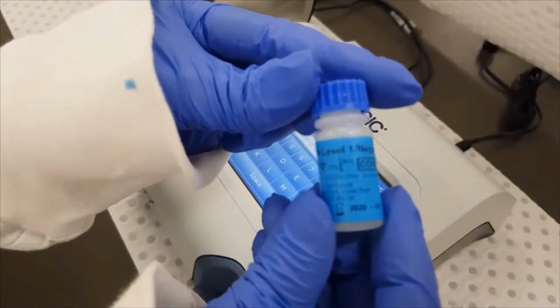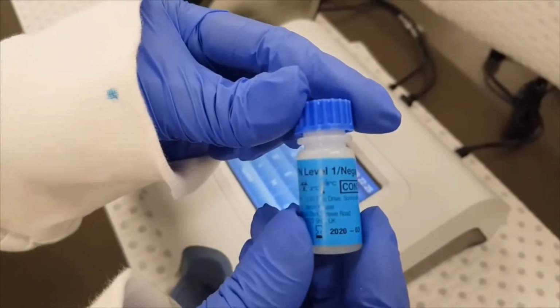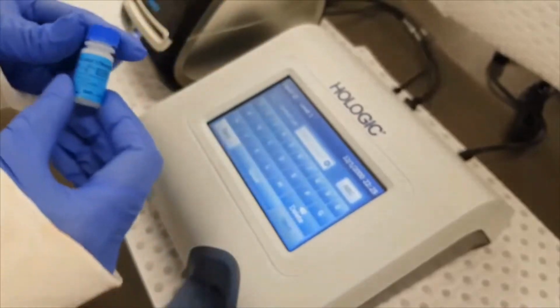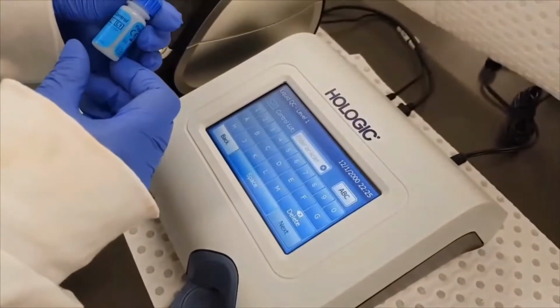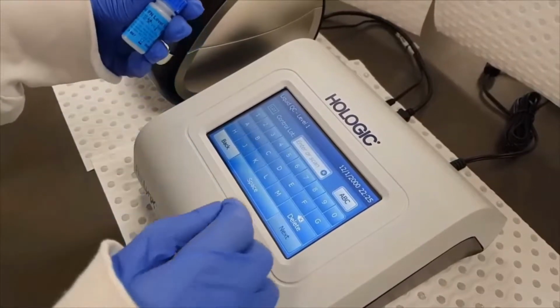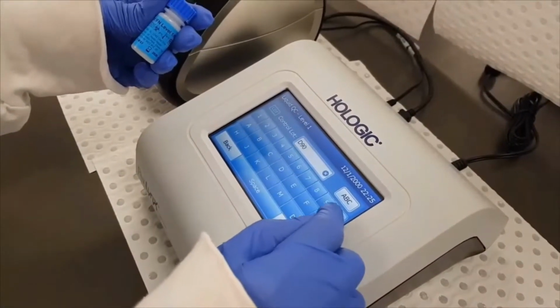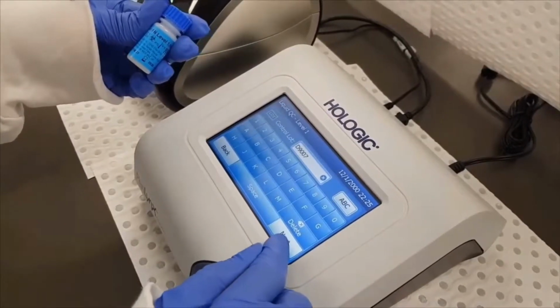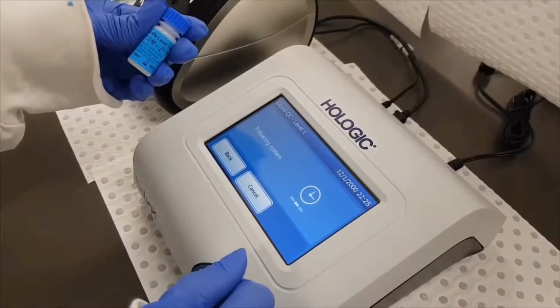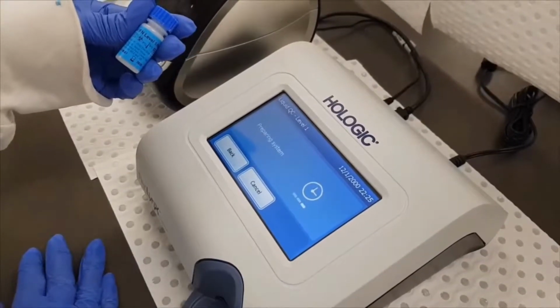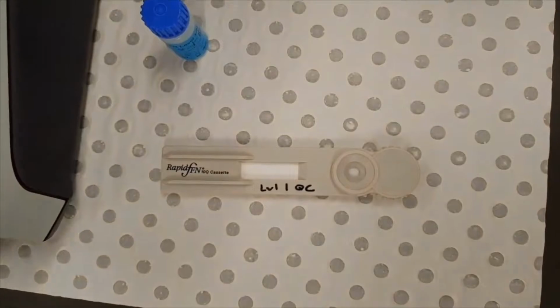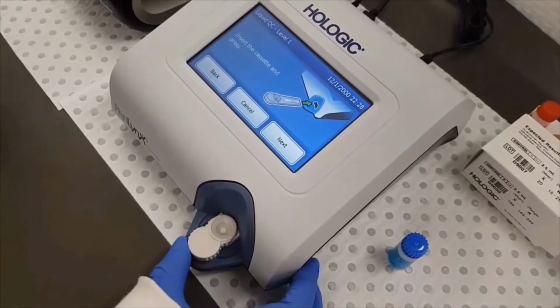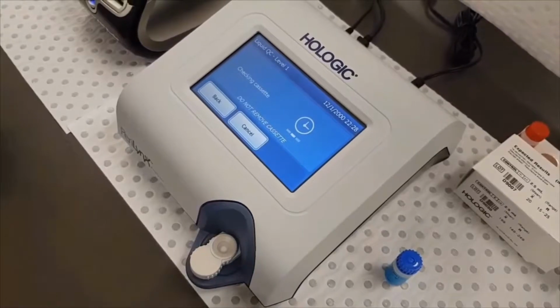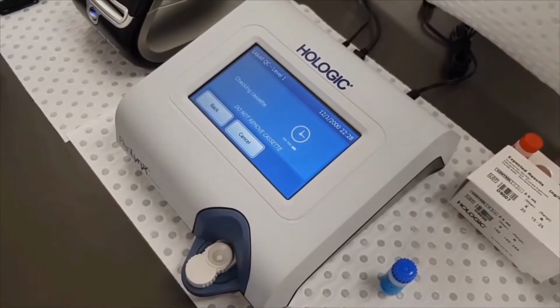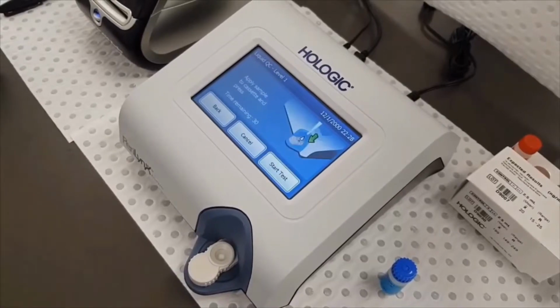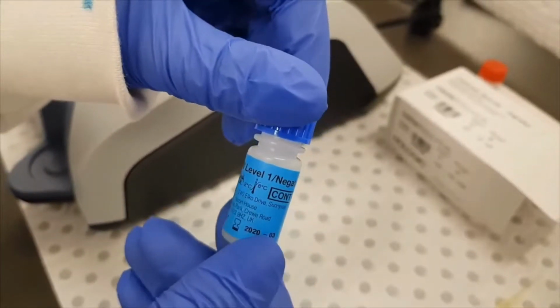On the bottle, you will find a clear label stating the control level, the expiry date, and the control lot number. Enter the lot number code in the system and press Next. Label the cassette and insert into the analyzer without the reagent and press Next. The system is now prepared for the addition of a level 1 control.